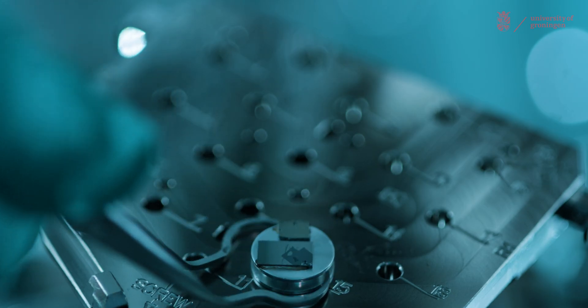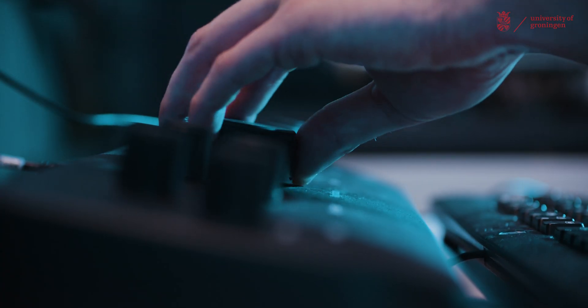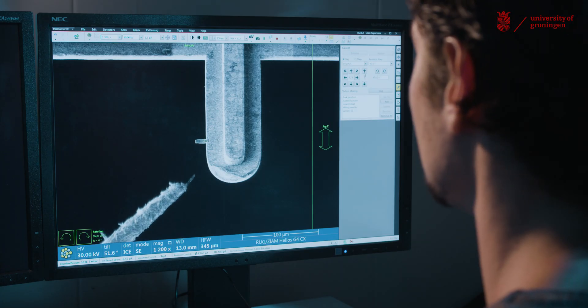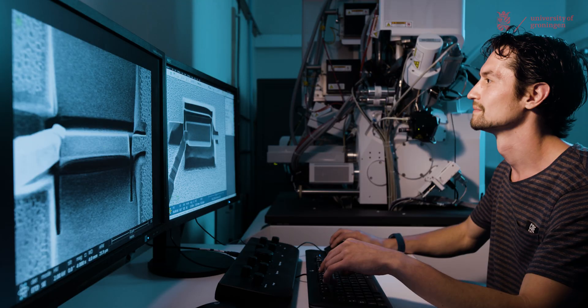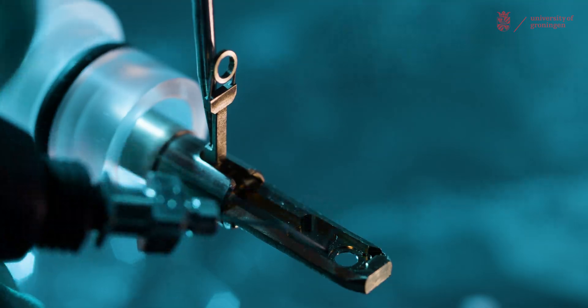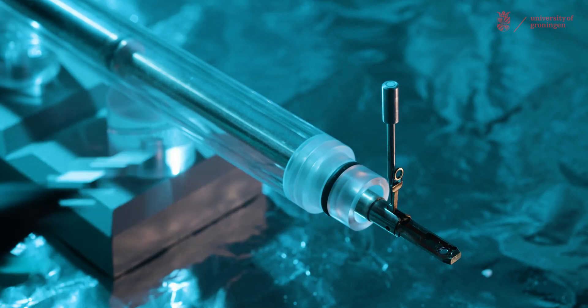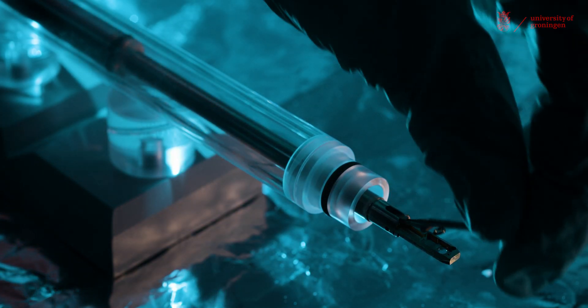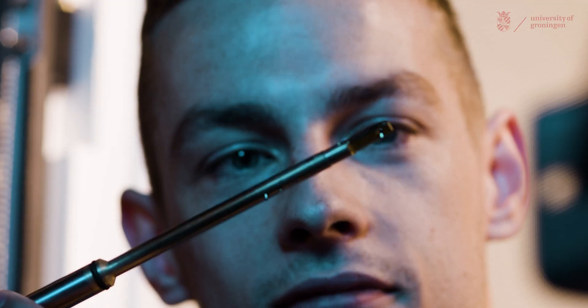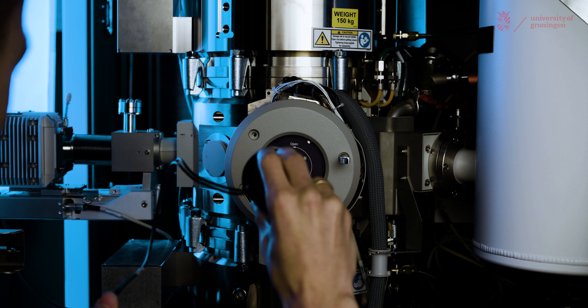Preparing samples for this transmission electron microscope is very crucial because the quality of the sample determines the final quality of the image. We have another system which contains a scanning electron microscope and a focused ion beam. We can see all kinds of locations on the sample and cut very thin sections out — thinner than 100 nanometers. Our hair is about 50 micrometers, so this is really a thousand times thinner than a hair. Then we can put it in our transmission electron microscope and image them.